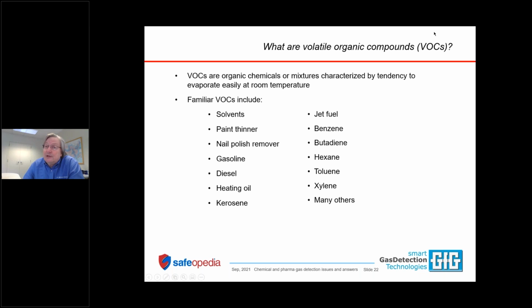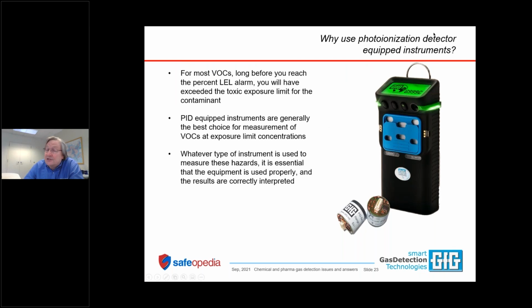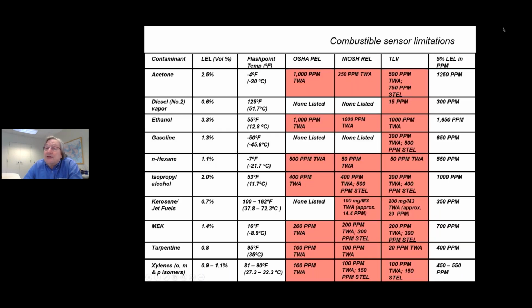VOCs figure prominently at chemical plants and especially in laboratories and pharmaceutical plants. So what is a VOC? It's a wide category that includes everything from jet fuel and diesel to specific chemicals like hexane and toluene, butadiene, xylenes, and benzene. So if you have these VOCs on site, then instead of a 4-gas instrument, probably you should consider adding sensor number 5, which is going to be a PID sensor that will allow you to take action and sound the alarm when you hit the toxic exposure limit, rather than waiting to hit the percent LEL, lower explosive limit concentration alarm.